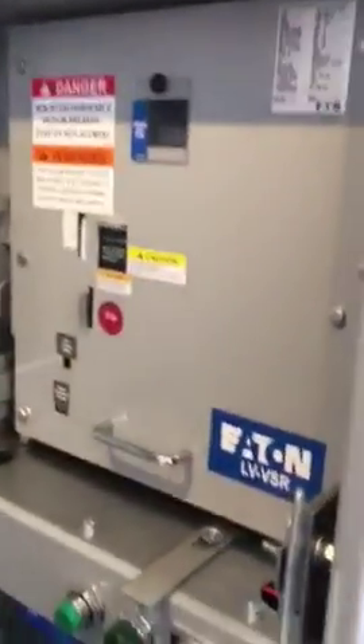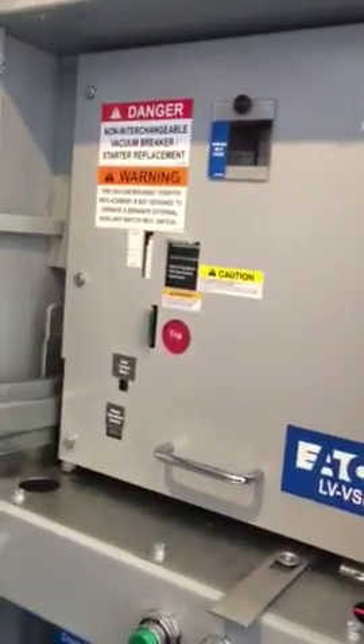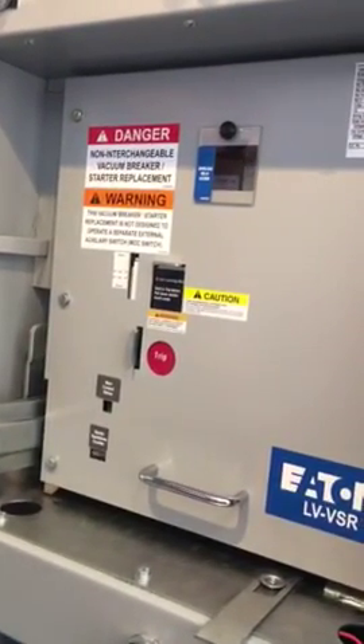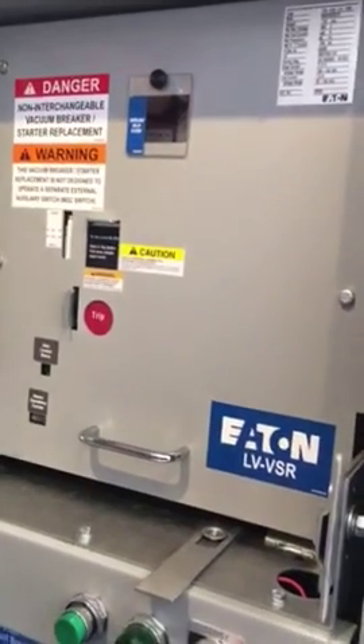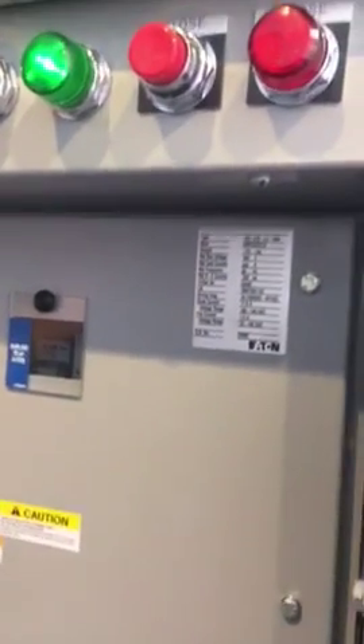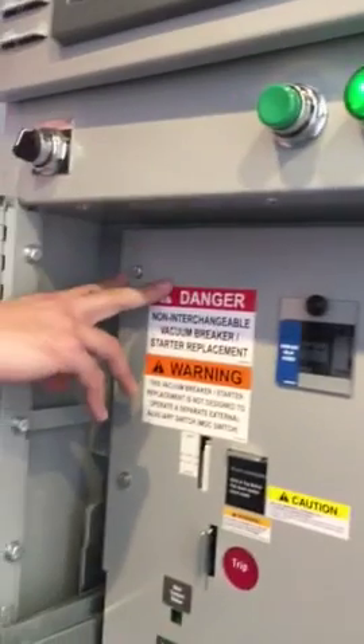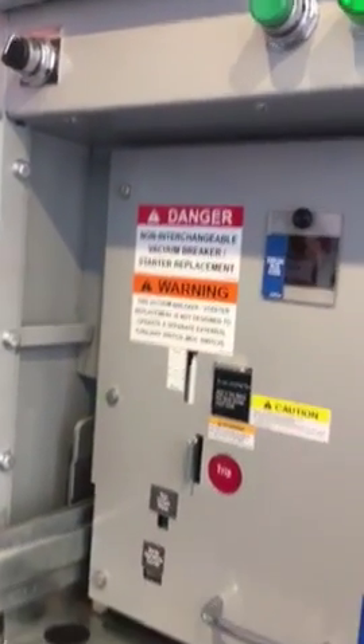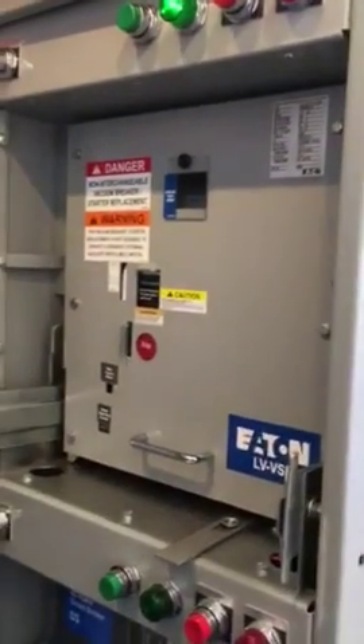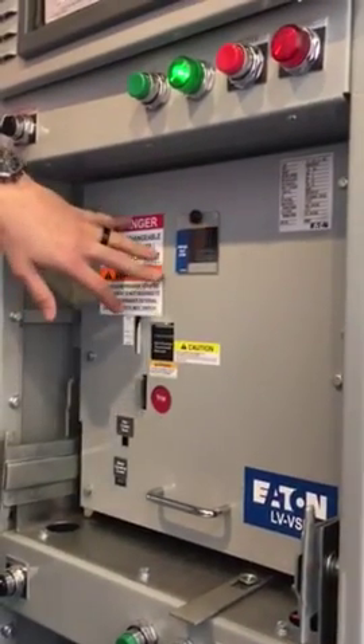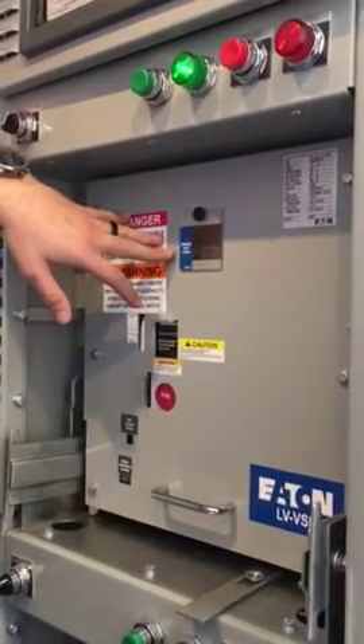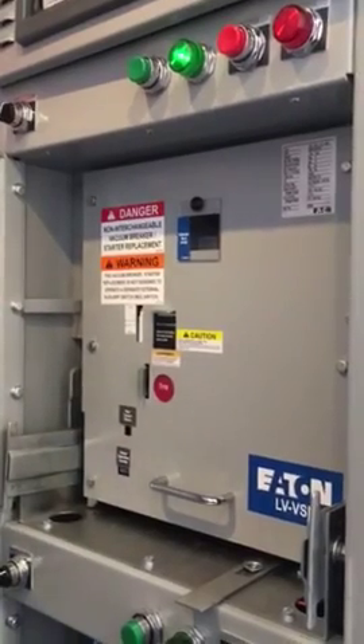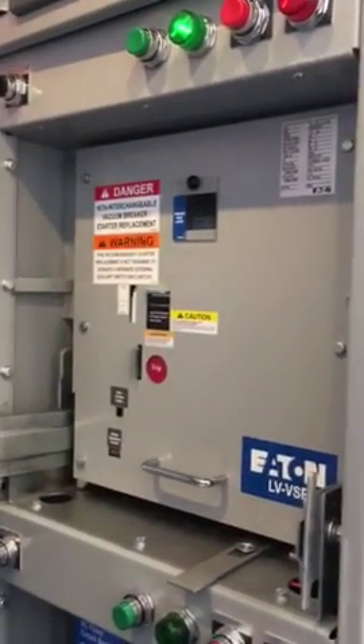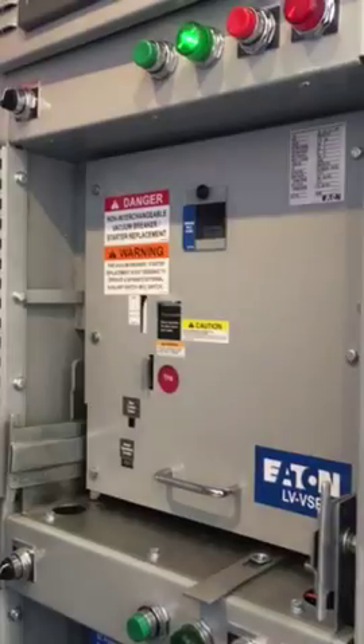In the second section here, we have this breaker converted over to a vacuum starter for motors. Something we see very frequently where old facilities are using circuit breakers to actually start and stop motors. The vacuum bottles that are in this device are much better, much more suited to working with motors than the original softer contacts on a breaker. The vacuum bottles are hundreds of thousands of operations. Breakers are more in the thousands of operations. So that's the big value discussion for these first two items.